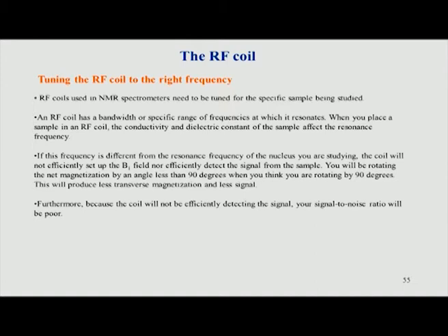Many elements of the entire periodic table are amenable to NMR spectroscopy, and therefore one has to generate frequencies tuned to the frequency of a particular nucleus. For example, when I say 500 megahertz, that is the frequency of hydrogen, but for carbon it will not be 500, it will be 125 megahertz. Similarly, for nitrogen it will be 50 megahertz.